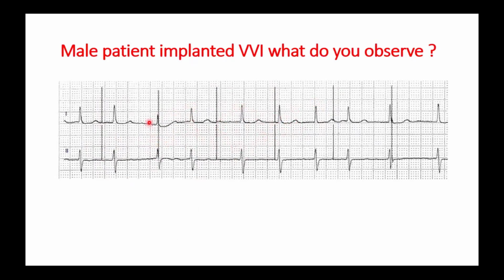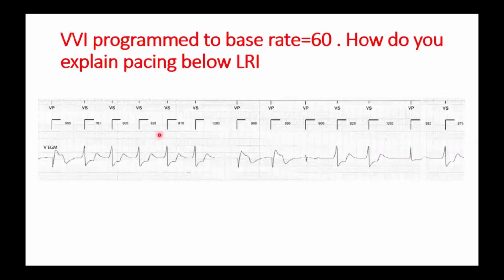Whenever the intrinsic beat occurs, it doesn't reset the timing. Also, when the pacing spike occurs in the baseline, there is no capture. So this is a typical ECG of a pacemaker that has a failure in capture and undersensing of the ventricular lead.